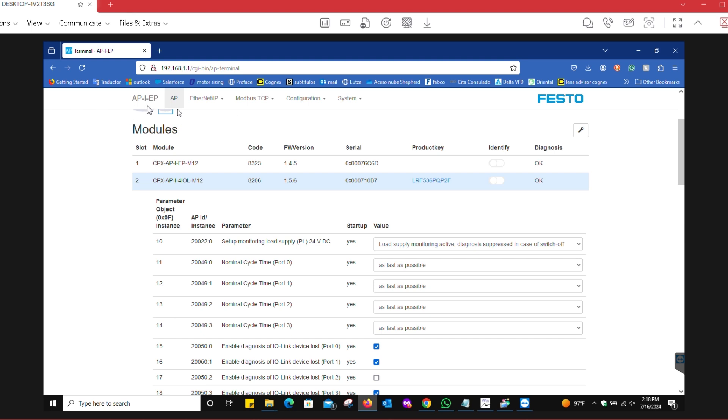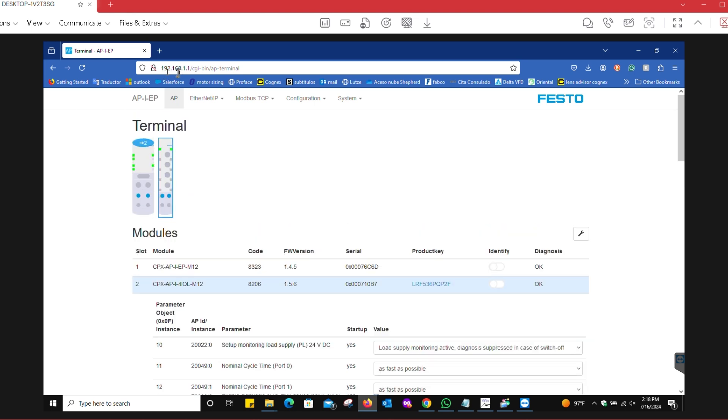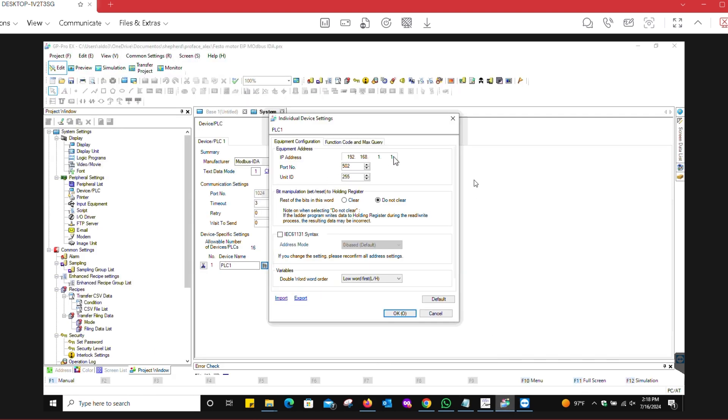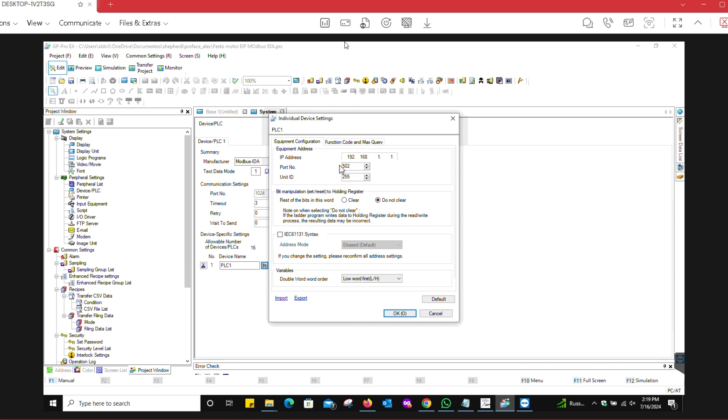The basic things that you have to configure: this is the IP address of this module, the CPX API EP module. That's the IP address of that module, 192.168.1.1. The port number is 502, that's the default. Unit ID you can leave as default 255, or change it to one. You could also change the word order, but in this case we left it as is.